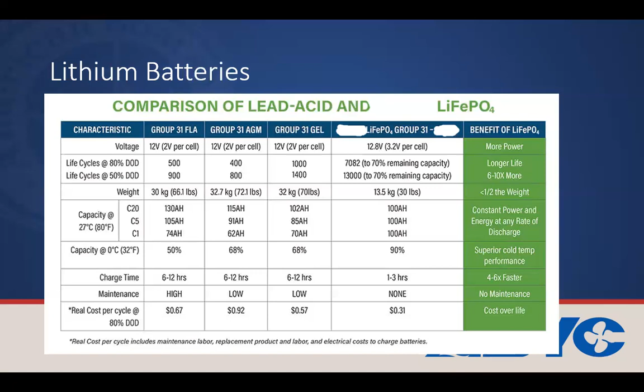You can discharge a lithium iron phosphate down to, typically, about 80% usable, whereas with lead acid, a lot of times you're only using the top 20, 30, 40% of that battery if you actually want to take care of it. So you can have less battery on the boat because you can use more of it. Maintenance-wise, there's really not a lot associated with lithium. Lead acid, depending if it's sealed or not, could have some maintenance there.